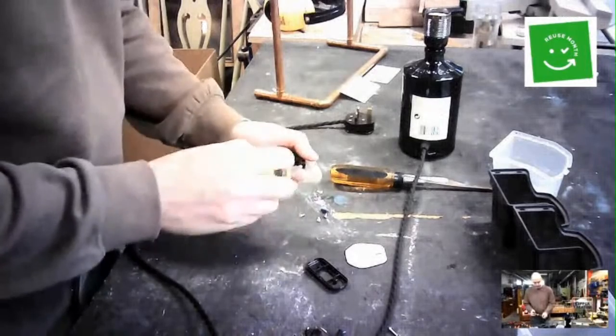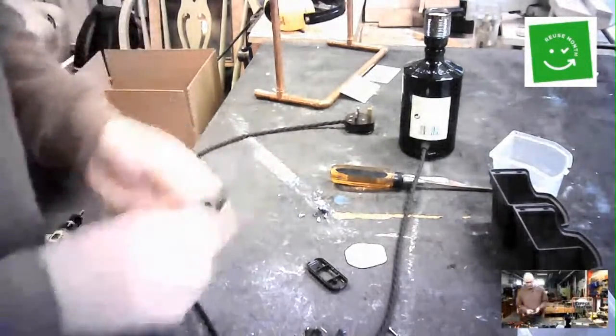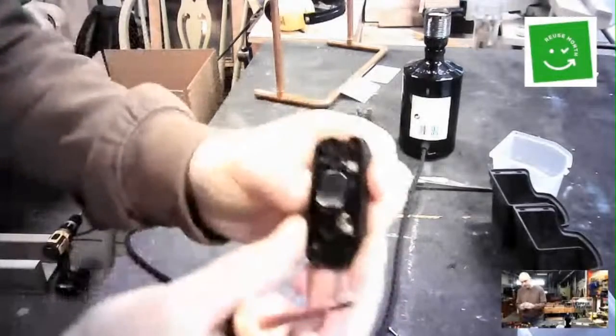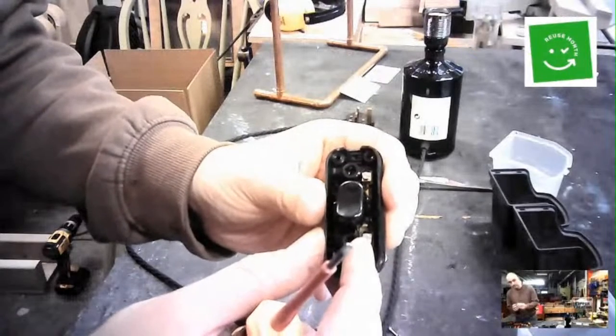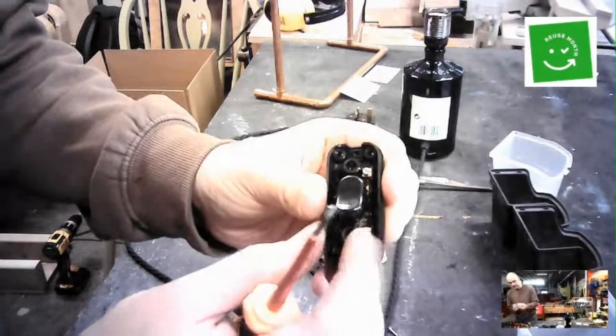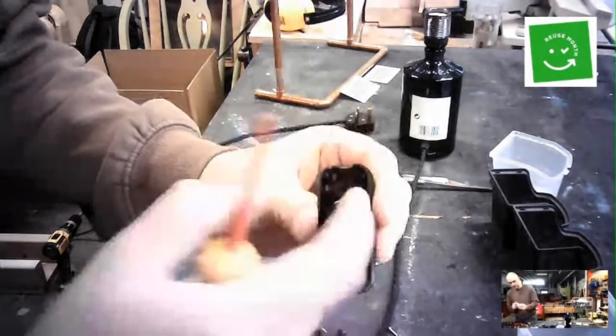It's just something that I've come across over the last few years. You don't necessarily always need to cut your cable. It's more safe when it's uncut as well. So I remove the brass connector for the neutral and for the earth. That then just leaves our live connectors. So we'll cut the live, we'll trim the cable back, pair it up, and then we'll connect in here. And we'll run the neutral and we'll run the earth just down the channel. And that's perfectly safe.